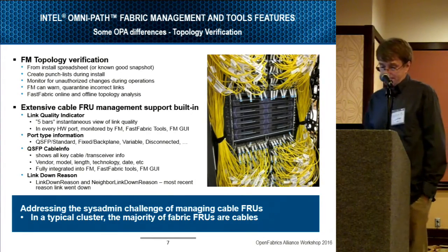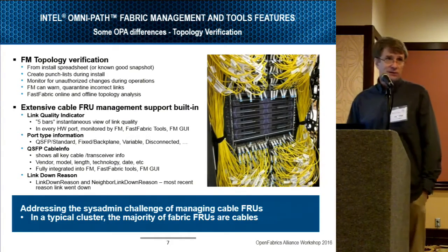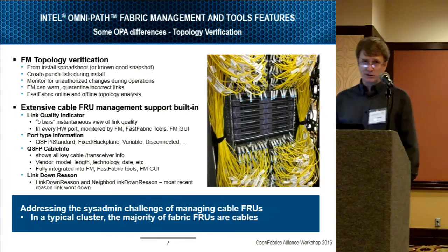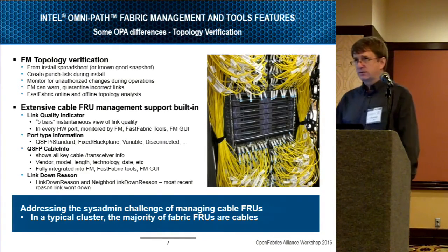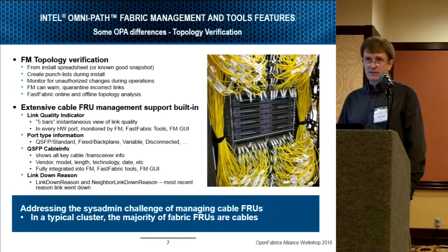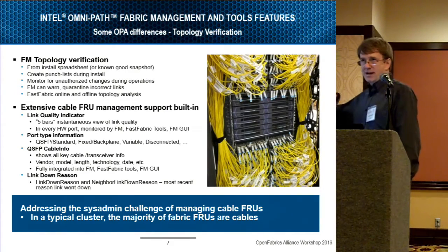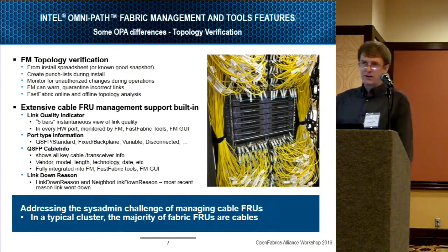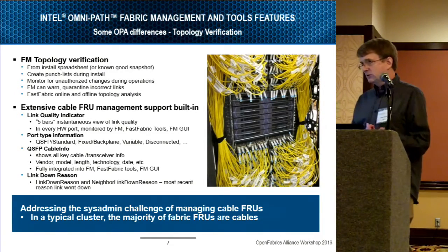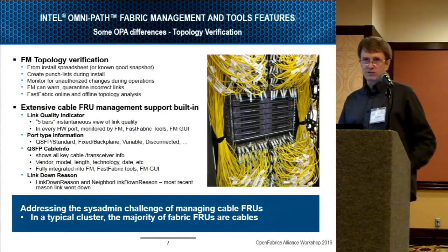One of the admin challenges is cable management. Cables have serial numbers, part numbers, etc. One thing that really helps with fabric installs is being able to put your cabling diagrams into a spreadsheet in advance, and then have the fabric manager tell you whether what it's looking at matches what's in there — and if not, produce punch lists that go out to the installers to fix cables or correct connections.